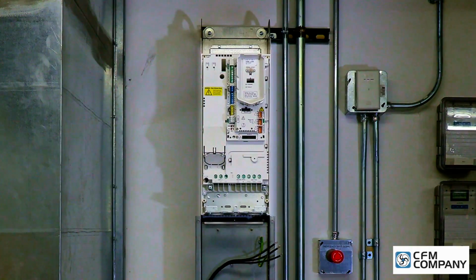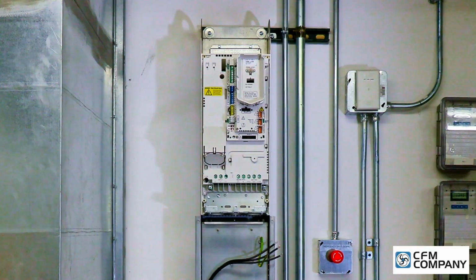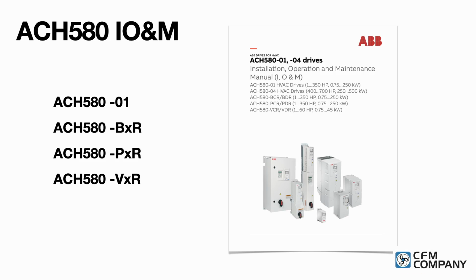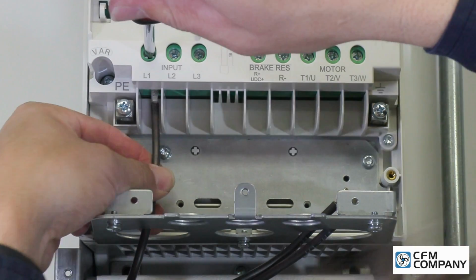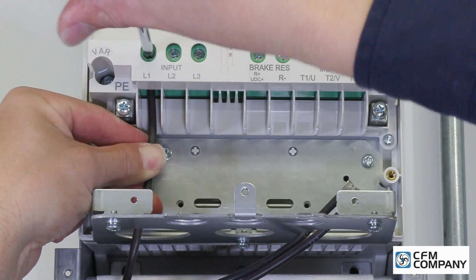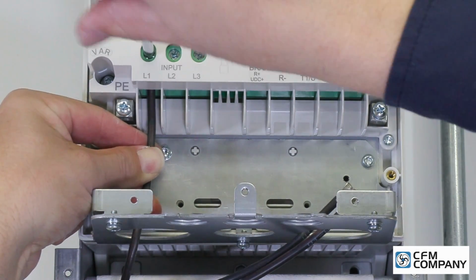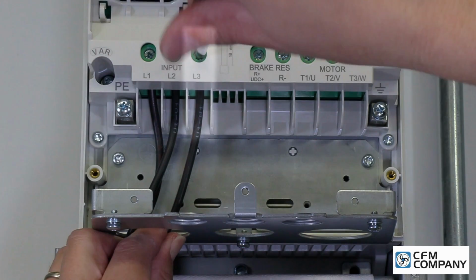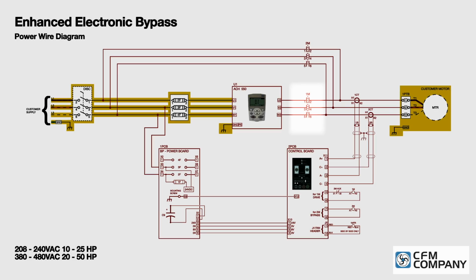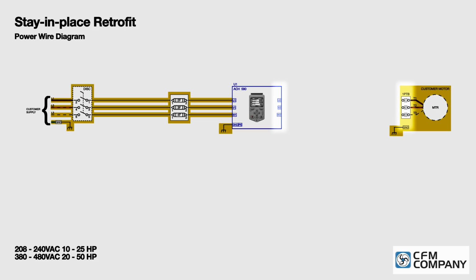The new ACH580 drive is shown already installed. The installation process is beyond the scope of this video. Installation was performed following the installation instructions found in the IOM that was shipped with the new drive. Starting with the three-phase line-side power wires, terminate the drive input wires to L1, L2, and L3. With the removal of the drive output contactor 1M, new three-phase conductors will need to be cut to length.